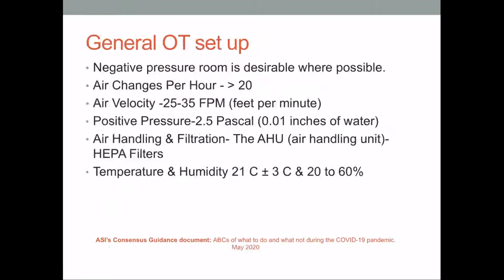We need precautions to prevent healthcare workers from getting infected, and the general OT setup should follow certain standards. In the hospital, there are two areas: a negative pressure room and a positive pressure room. In a positive pressure room, pressure inside is greater than outside, which is basically seen in the operation theater. In a negative pressure room, pressure inside is less than outside, so infective particles are not transmitted outside. Ideally, isolation rooms in the hospital are negative pressure rooms.